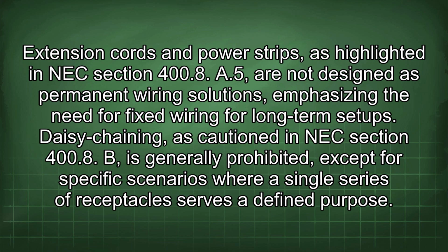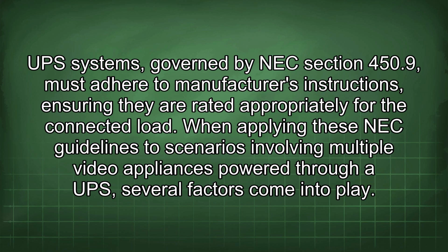Daisy chaining, as cautioned in NEC section 400.8(b), is generally prohibited, except for specific scenarios where a single series of receptacles serves a defined purpose. UPS systems, governed by NEC section 450.9, must adhere to manufacturer's instructions, ensuring they are rated appropriately for the connected load. When applying these NEC guidelines to scenarios involving multiple video appliances powered through UPS, several factors come into play.